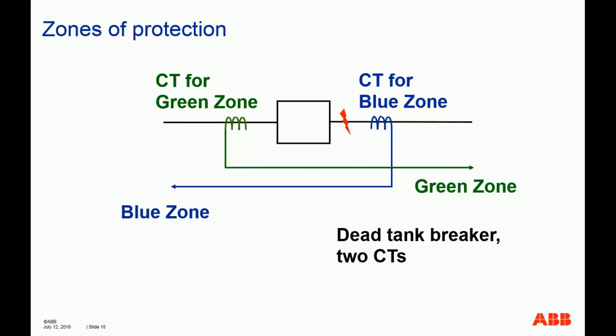However, when the breaker is already open, because sometimes, as I mentioned, in this type of station, the two main transformers connected to it, for example, imagine the two transformers here, they usually are rated to carry the full load of the bus, right? So theoretically, the tiebreaker is normally operated as normally open, so you don't close this tiebreaker. In that case, imagine you have a fault here, okay, and obviously the blue zone, the blue bus relays will operate because the fault falls in its zone, right? And the green zone will also operate, based on the contribution from the transformer, from whatever other sources there may be. However, the problem is, if the breaker is open, this blue zone doesn't really need to operate, correct?